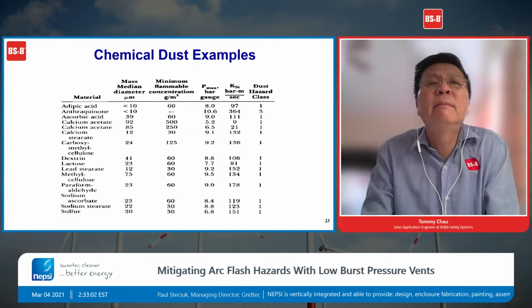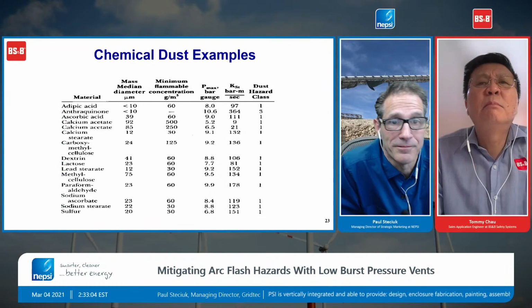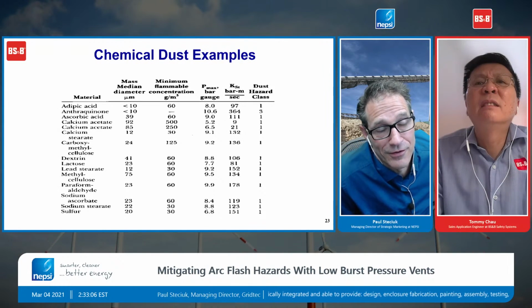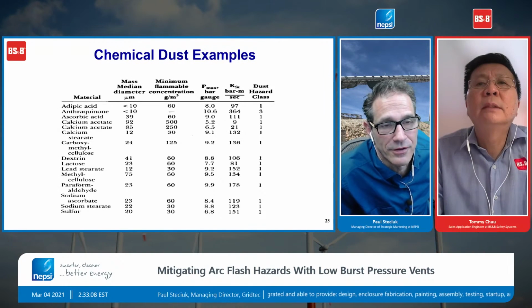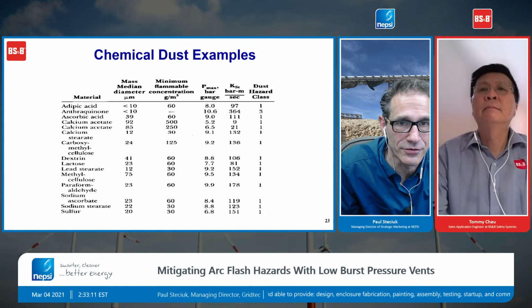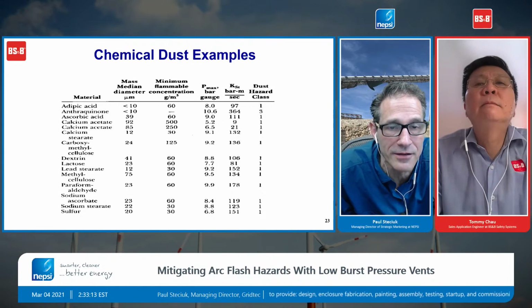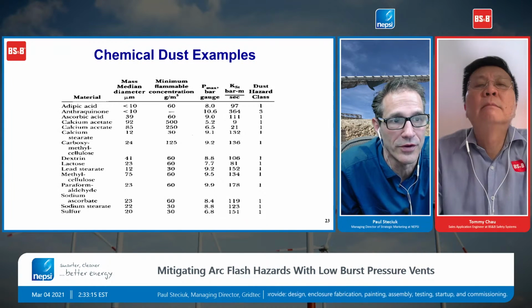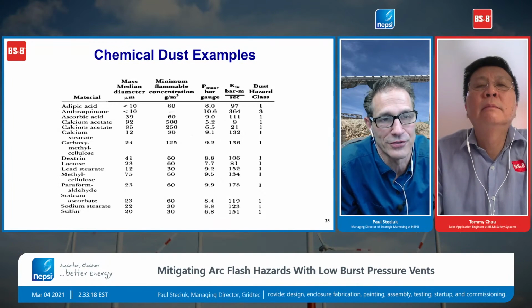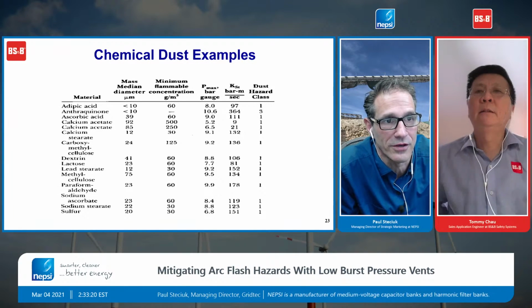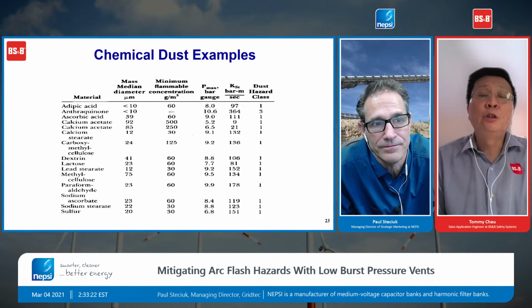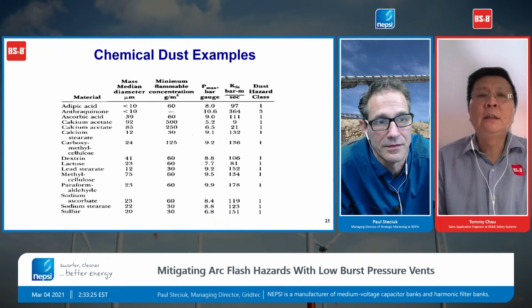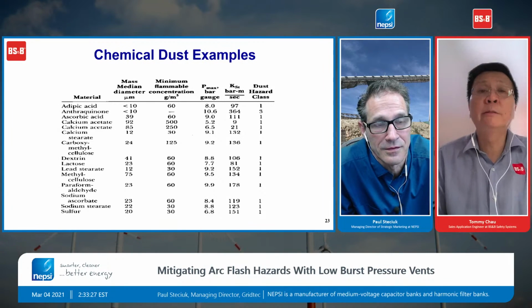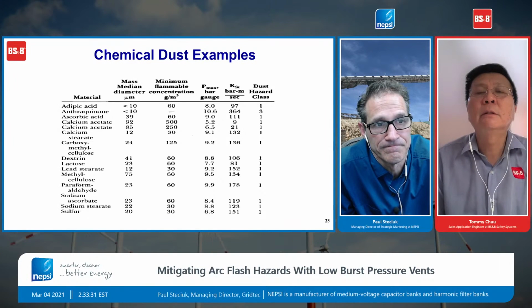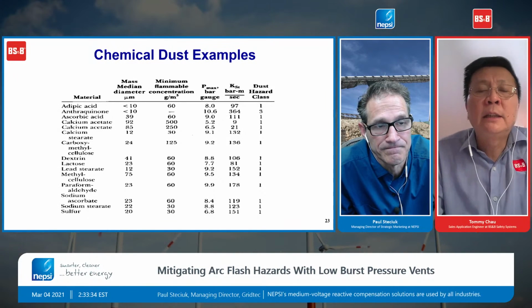And eight bars is a lot of pressure. Eight bars is basically eight atmospheres, and that's a lot of pressure. Fifteen times 8 pounds per square inch over an area, and if you think about pressure over areas, it adds up very quickly. As you know, Paul, we talked about this. The common burst pressure for an explosion vent is 1 to 1.5 psi. So obviously, that's the idea behind it.